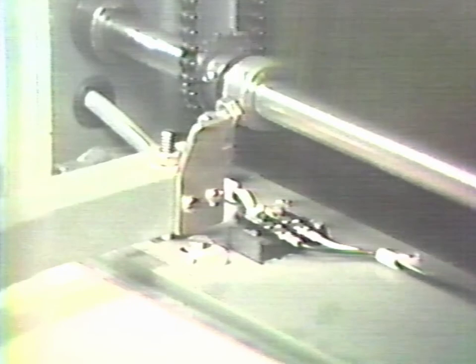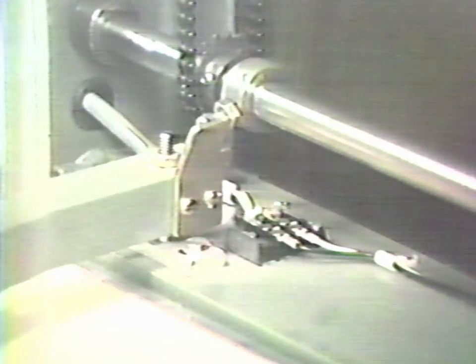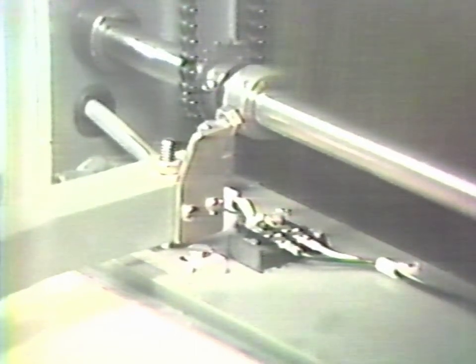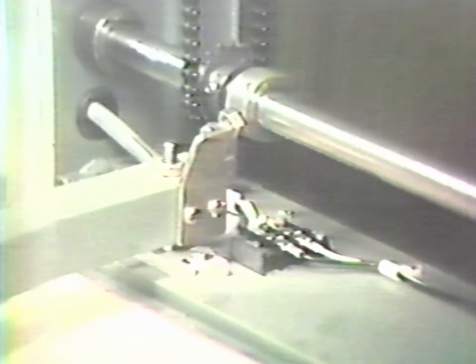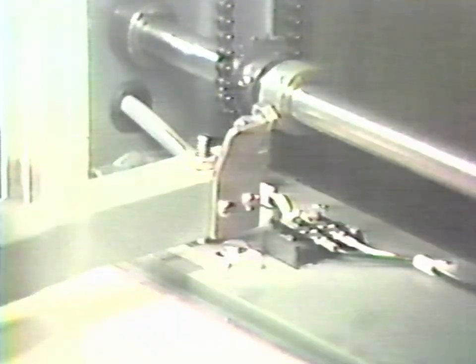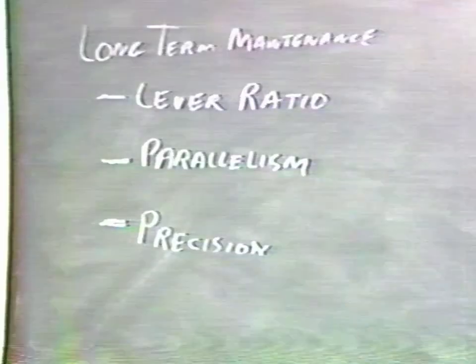The adjustment of the length of the screw controls the amount of motion. Since the motion is very small and in fact is not critical, it is not usually necessary to adjust the screw. However, sometimes the arrestment bar itself, which is mounted on a pivot, may come off the pivot and would have to be replaced. It is merely a two-pointed screw.